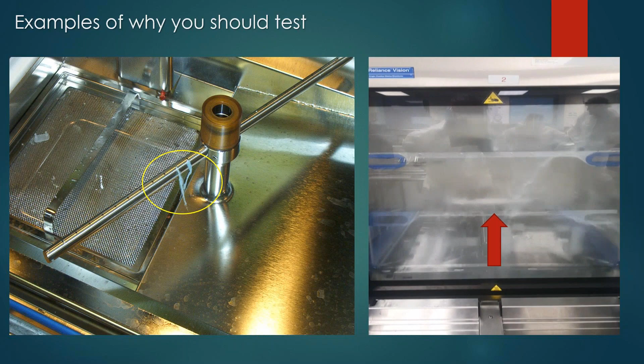Here is a good example of why to test, and this also relates back. That's actually blue wrap right there in the picture on the left. Things get shredded as they go through that screen, and then they come into the spray arm. And as those spray arms get clogged, they're not going to perform properly, and they're going to start failing tests. I want you to take a look, as this video starts, at the middle spray arm just above the arrow. Now, it's hard to see the other ones because they're traveling so fast, because that's the speed they're supposed to be going at. And that middle spray arm is clogged, and that is what is causing it to move across the frame at a snail's pace. So when your spray arms get clogged, they're not producing the same effect that they should throughout your cycle.